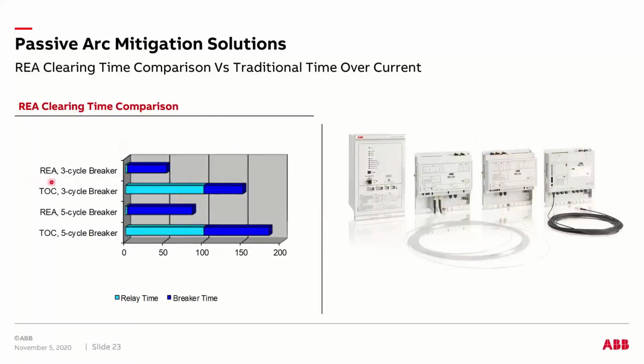So this is another comparison using an REA relay with a 3-cycle breaker, where you have about 50 milliseconds of reaction time, compared to a time overcurrent relay with a 3-cycle breaker. When it is clearing an arcing fault, it could take up to like 150 milliseconds. Comparing that with a 5-cycle breaker, where it could take up to 80 milliseconds using an REA relay, which is an arc flash relay. And if it's a time overcurrent, we are well over the 120, 150, close to like 200 milliseconds, at which point you have already done significant damage within your equipment.